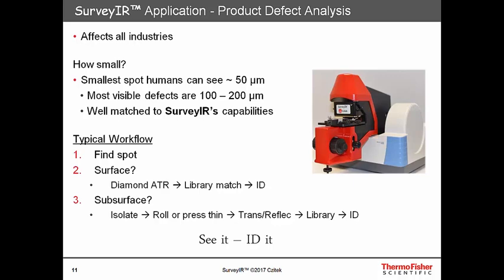We can analyze both types of samples with SurveyIR, but the approach is slightly different. With a surface-located spot, it is best to attempt the analysis with our diamond ATR, which is surface selective. This minimizes sample preparation and provides an easier analysis. Once we've collected the spectra, we try to match them against libraries of known materials. If the sample is subsurface, we need to isolate it and remove it from the product, put it on an infrared transmitting or reflecting substrate, roll or press it thin, and then measure it by transmission through an infrared transmitting window or by double-pass reflection off a low-e glass slide.